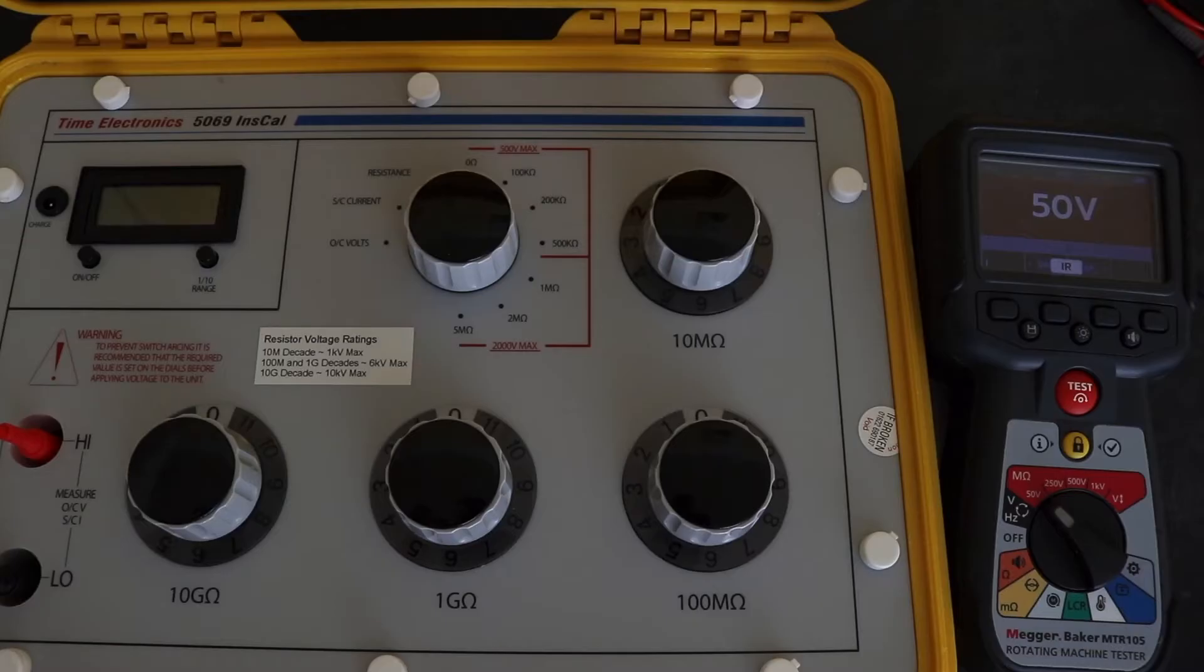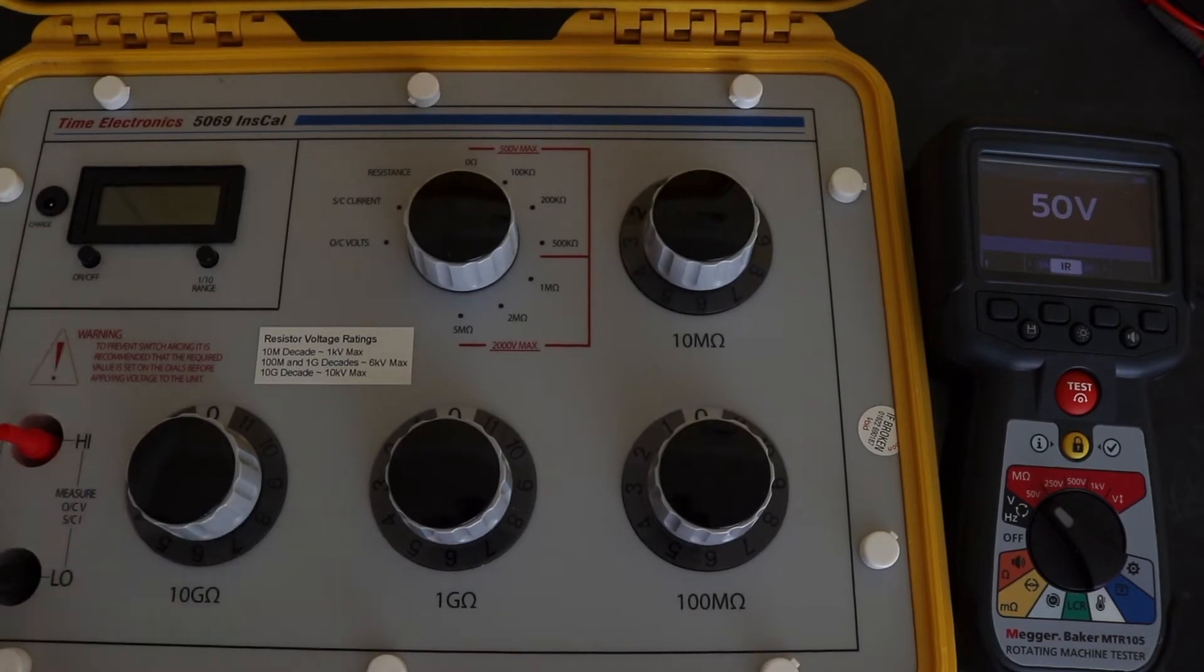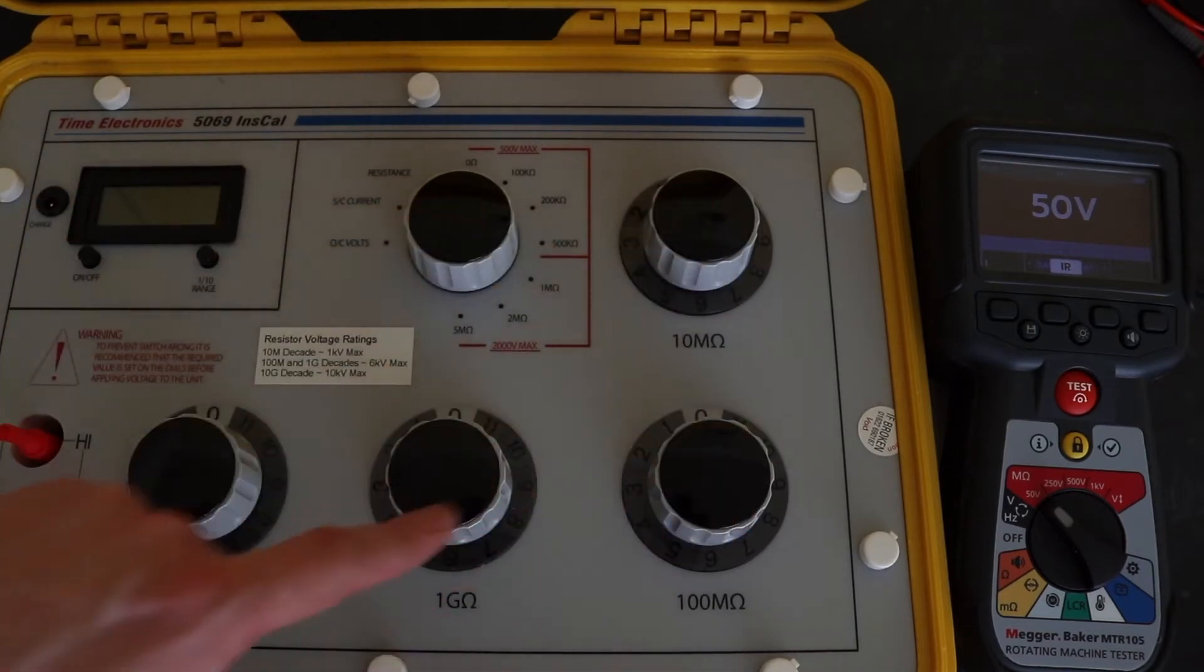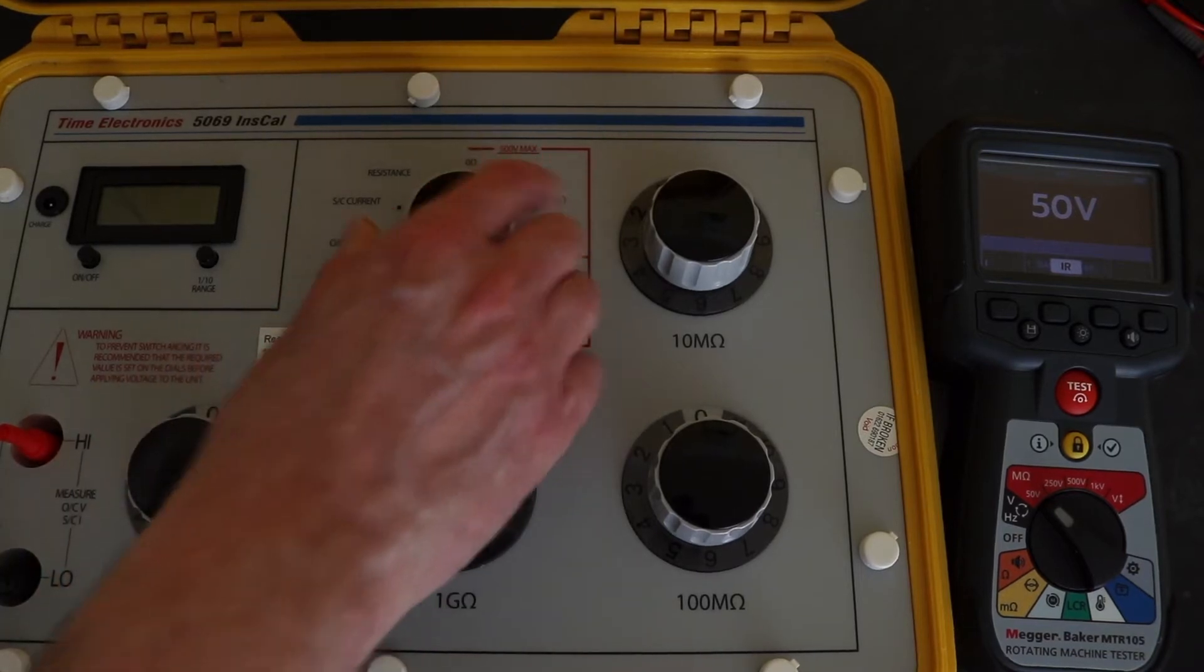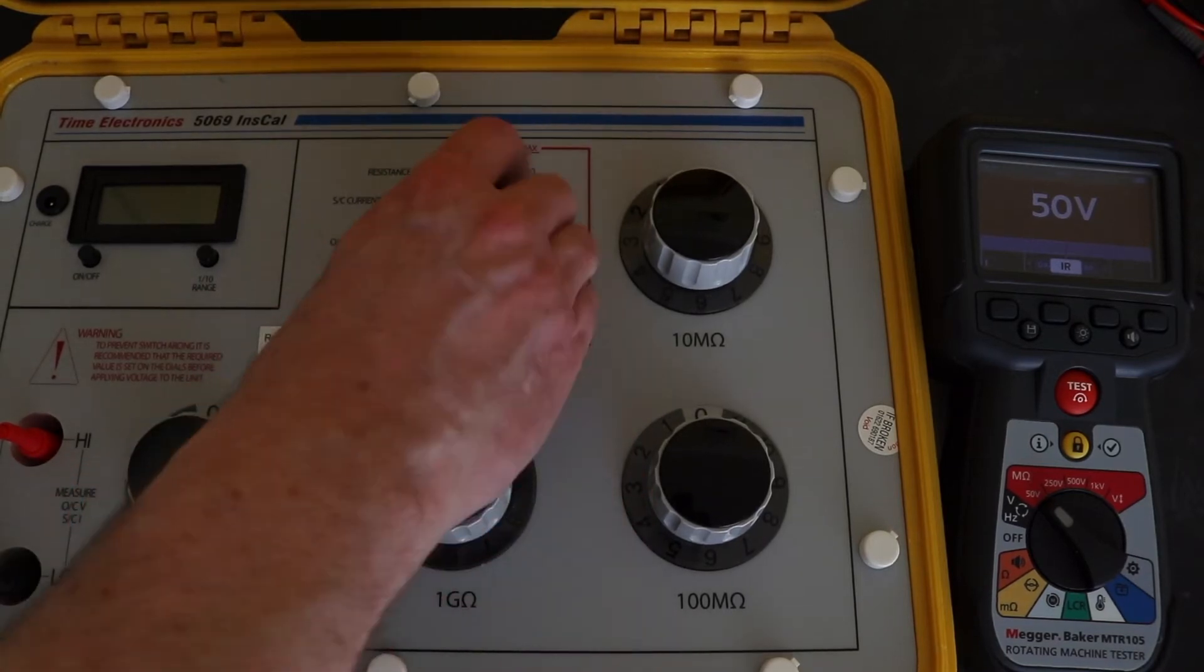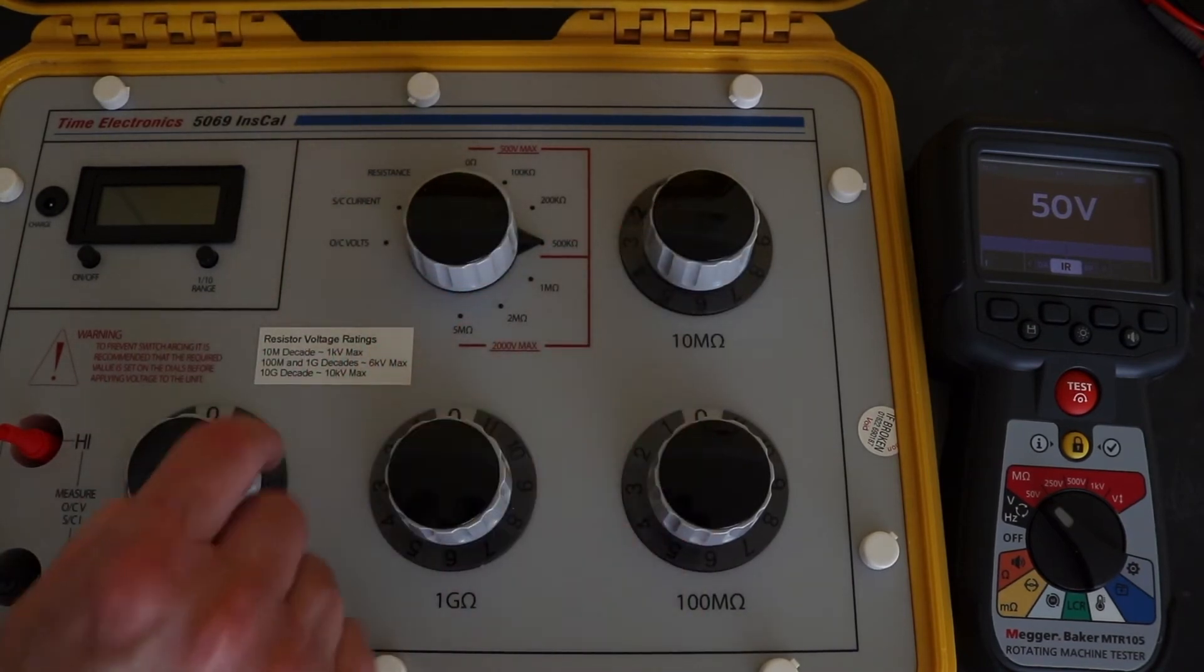Okay, so setup to carry out a resistance accuracy test on an insulation tester. The insulation tester is wired just to the input of the box over here. I set the control knob of the 5069 to resistance and then that gives me access to all of these decades to set whatever value I want to do. The alternative is to actually move this around and I have a few smaller fixed resistance values in here that I can use as an alternative to these actual decades.